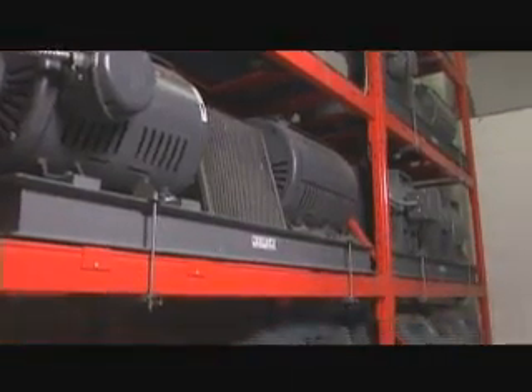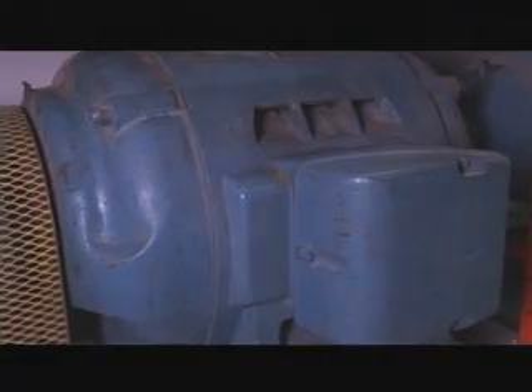Today I'll be running and loading this VFD up to full load 100 horsepower on a squirrel cage induction motor. This is the motor generator room and this is the 100 horsepower motor that is connected to the VFD that you saw in the H&E lab. The VFD motor is mechanically connected via its drive shaft to an identical squirrel cage induction motor here.